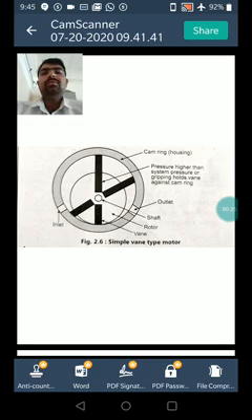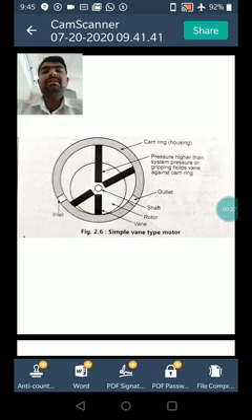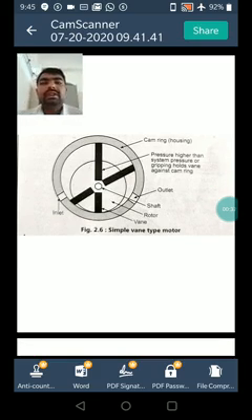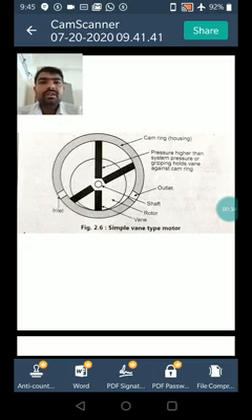Okay, in a vane motor the imbalance is caused by the difference in the vanes' area exposed to the hydraulic oil pressure, owing to the eccentricity between the rotor and housing. The unequal area of the vanes exposed to oil pressure develops a torque about the motor shaft. The output torque produced varies directly with oil pressure and vane area.